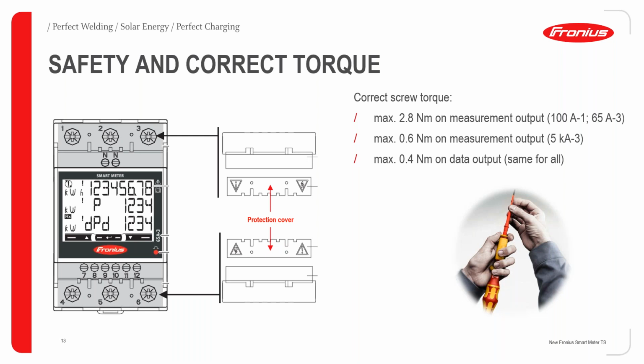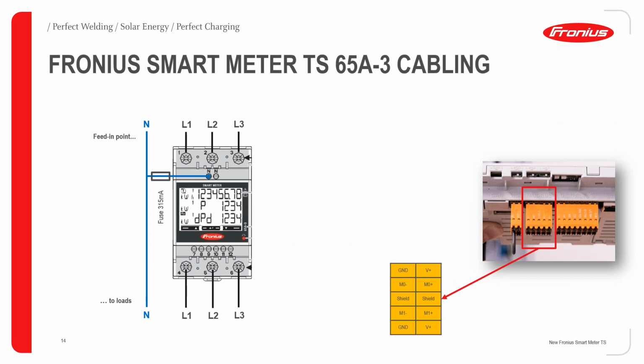And there is a protection cover whenever you are using these cabling of data cables. Please make sure the protection covers for the phases are closed, and then the sealable terminal covers are available. This is to protect all the terminals. So if you look into the connection diagram, there is a fusing option provided. If your local regulation demands it, it is not mandatory from Fronius side. In case there is a local regulation from your country that demands the fusing, then you can go for 315 milliamps. That's the minimum you can go for.